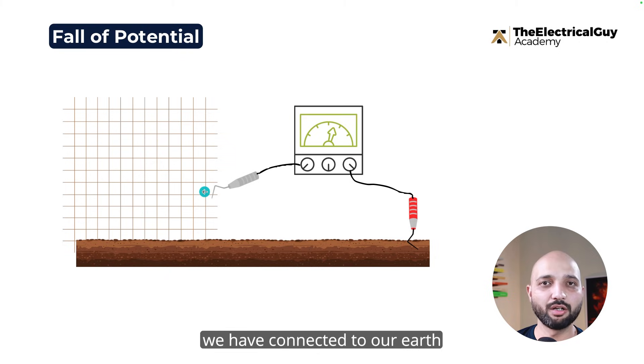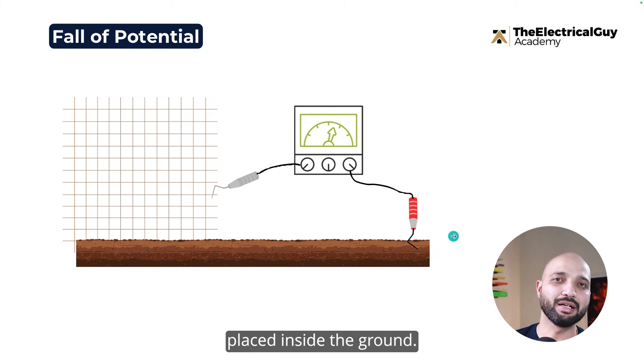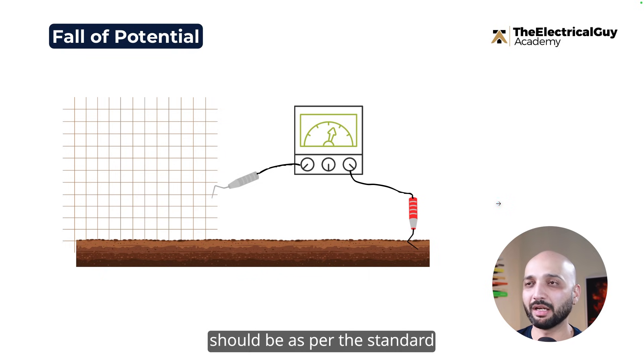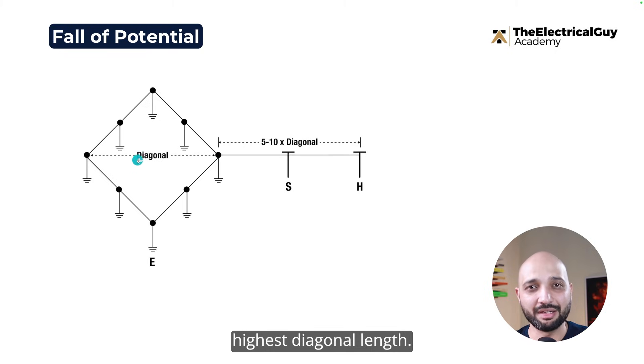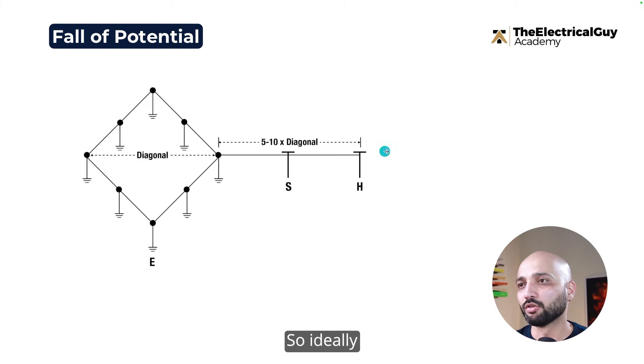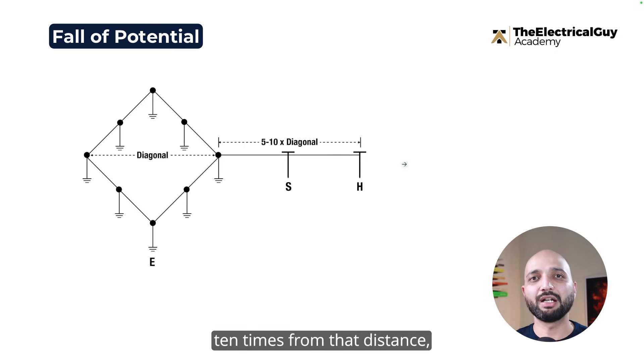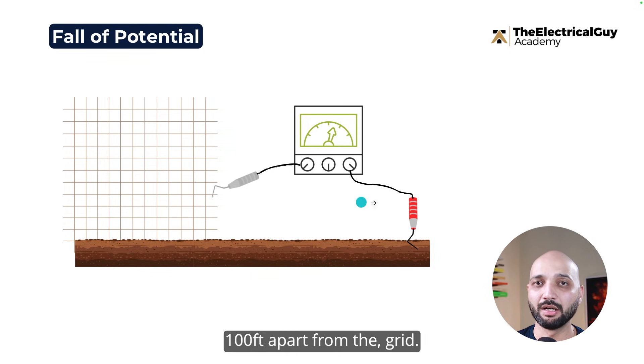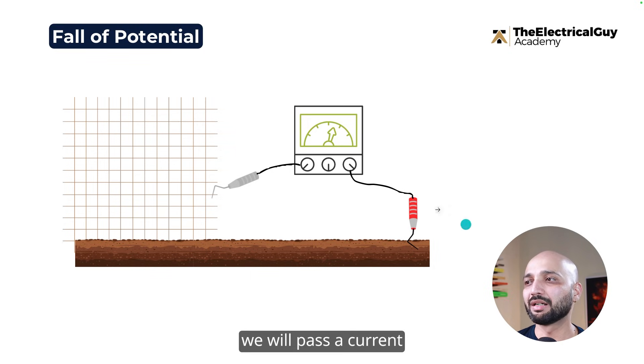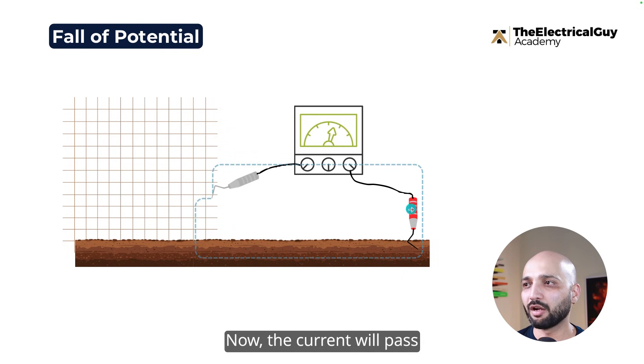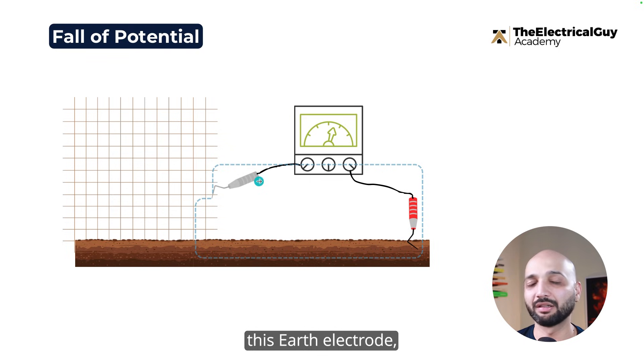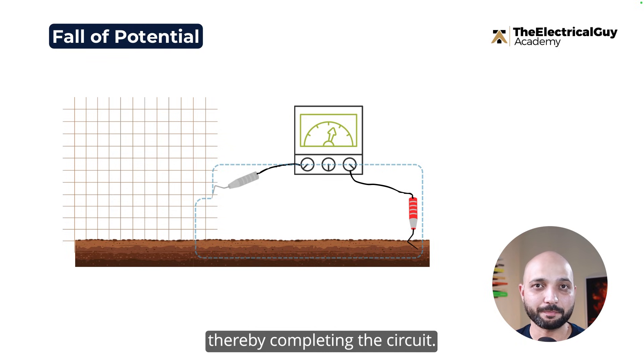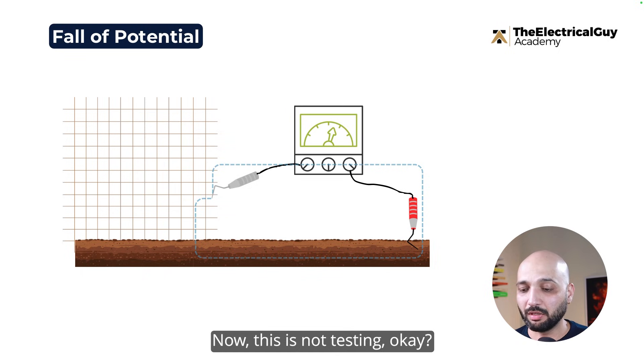The second electrode is placed in the ground. The distance between the two should be, as per the standard, 5 to 10 times the diagonal length of the grid. For example, if the highest diagonal length is 10 feet, you should place the test electrode around 100 feet away. We then pass a current through the test meter — the current travels through the earth electrode, through the ground, then to the earth grid, and back to the meter via the earth electrode, completing the circuit.